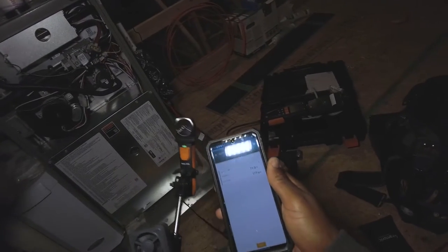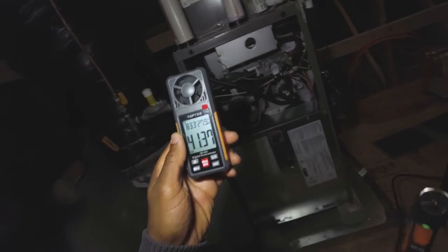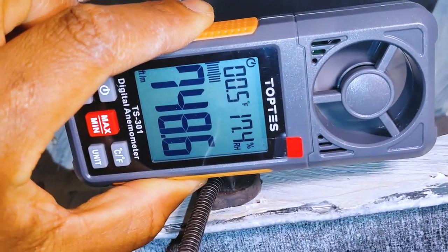As you can see, the Testo gives us temperature and velocity. The cool thing about this unit is it actually does everything — temperature, humidity, and velocity — everything but CFM. On the TOPTES, we're reading about 750 to 780 feet per minute.